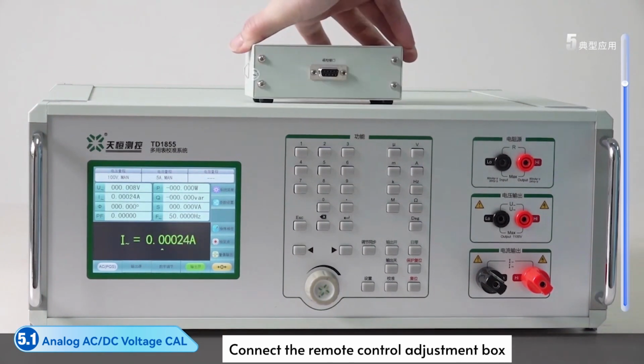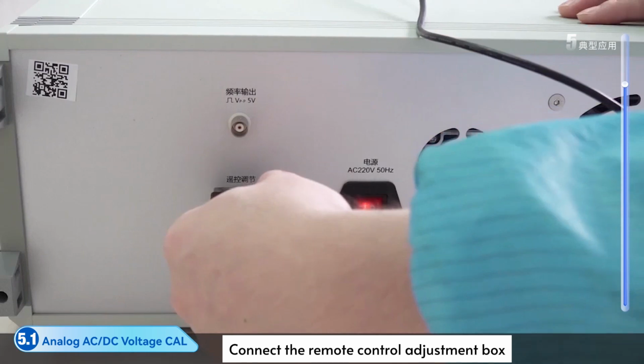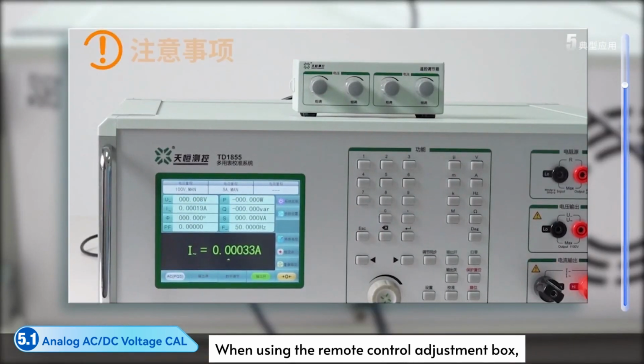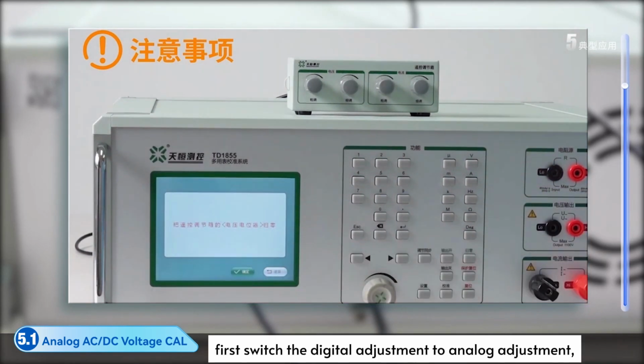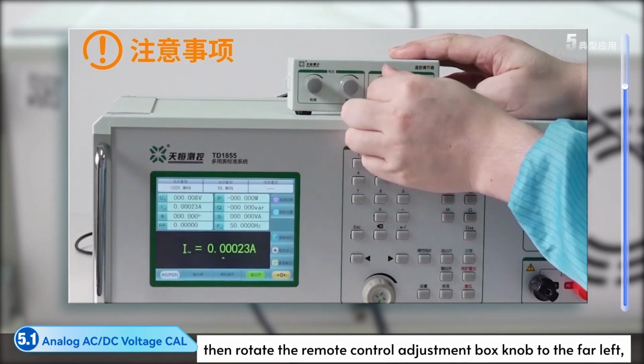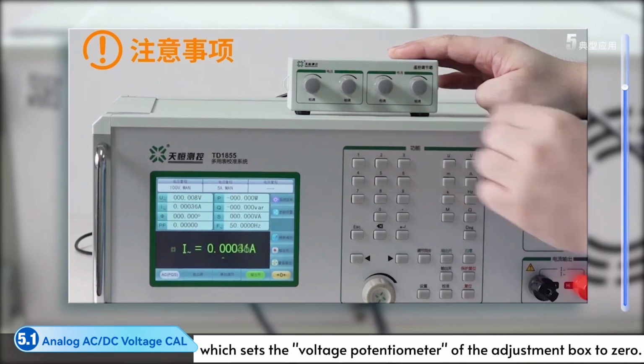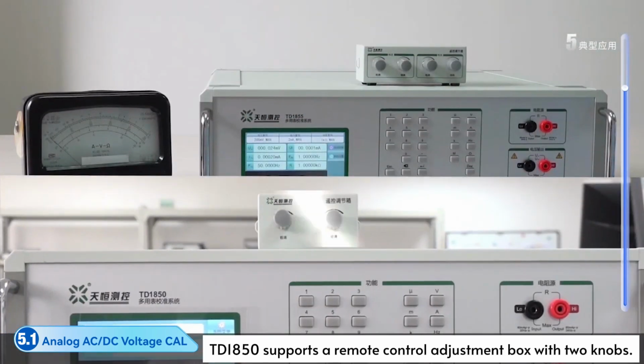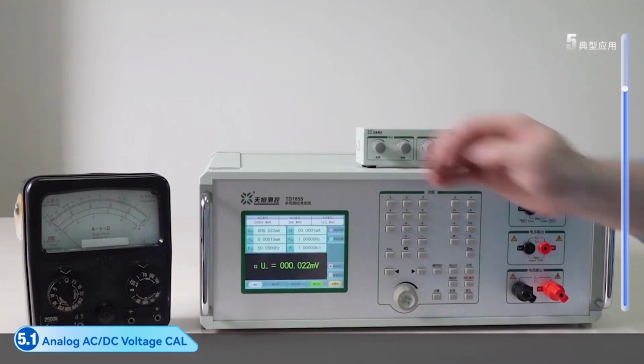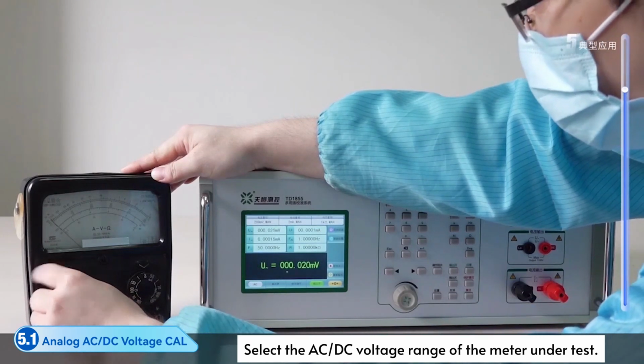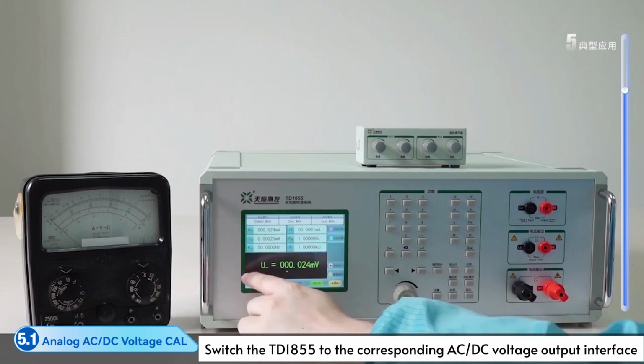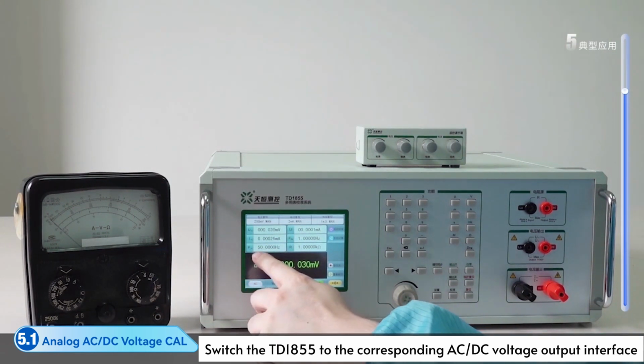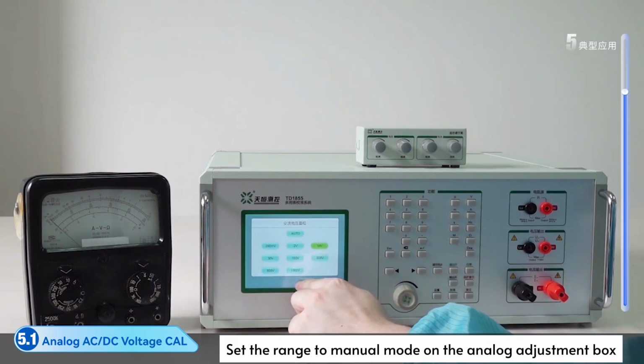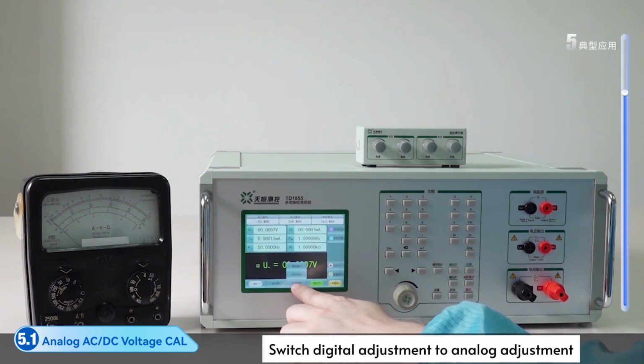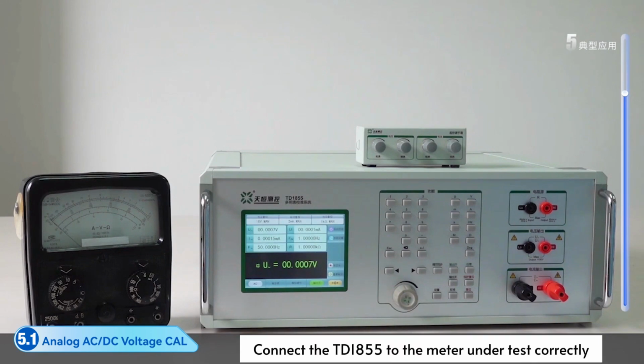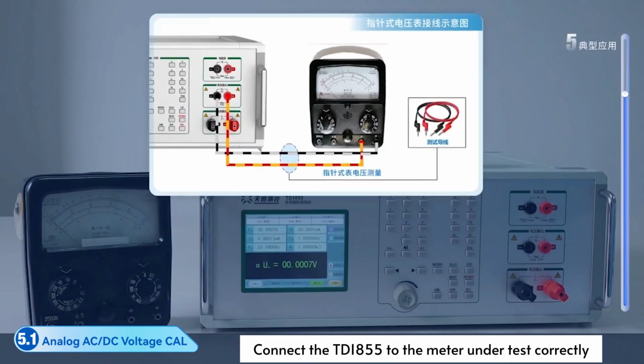Connect the remote control adjustment box. When using the remote control adjustment box, first switch the digital adjustment to analog adjustment, then rotate the knob to the far left, which sets the voltage potentiometer of the box to 0. TD1850 supports a remote control adjustment box with 2 knobs. Select the AC/DC voltage range of the meter under test. Switch the TD1855 to the corresponding AC/DC voltage output. Set the range to manual mode. Switch digital adjustment to analog adjustment. Connect the TD1855 to the meter under test correctly.